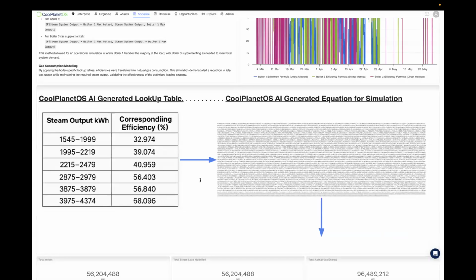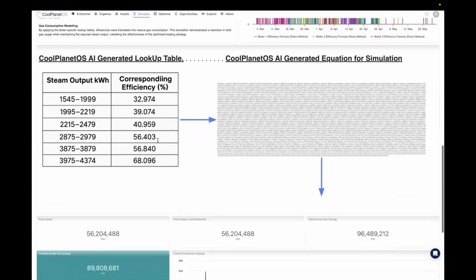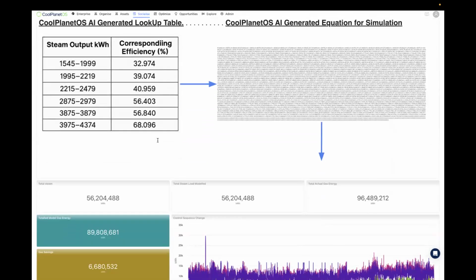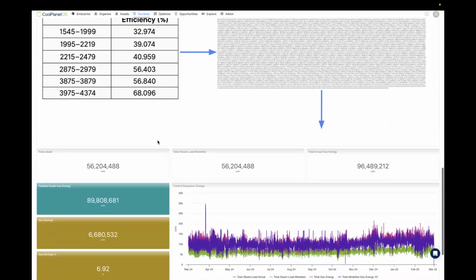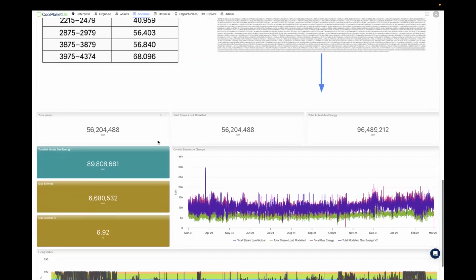What you can see on screen is the AI and our platform looking at the raw data over an annual period, at 1-minute granularity, creating a lookup table of steam output versus efficiency for each of the boilers. It's then coming up with a more optimized sequencing control output, and visualizing what kind of impact that change in control would have.